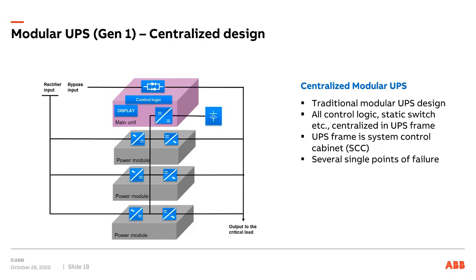So having talked about that, the next two slides are about when, and this is certainly after I entered the business, when we started developing modular UPSs. The first modular UPSs are what we would refer to as a centralized design. The one line you see on the left here is just with 3 modules. There are modular UPSs today, I believe, with up to 20 power modules that can go into the UPS frame. But the first, I refer to them as generation 1 modular UPSs, were centralized design, where the power modules were just the rectifier and the inverter, and everything else was fixed, installed in the UPS frame.